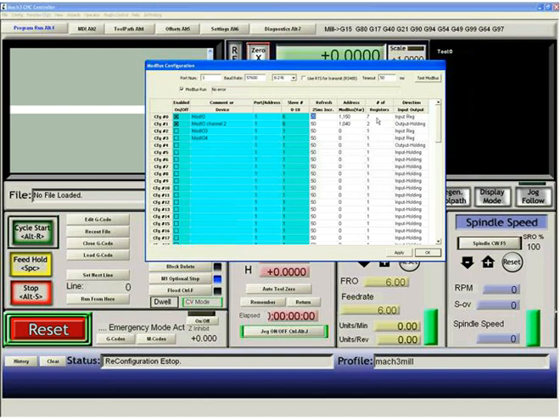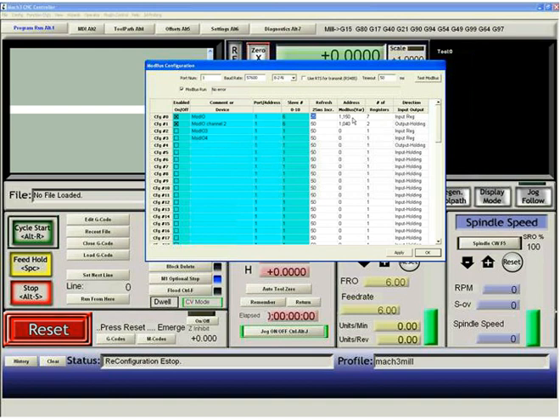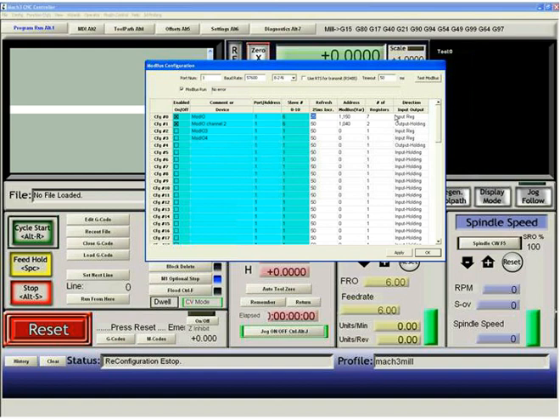So the first 7 16-bit words of the Modbus will be transferred in from address 1150 to addresses 0 through 6 on the plug-in Modbus, which is what I've named it. Plug-in Modbus registers in configuration 0. This will all make better sense in a moment.